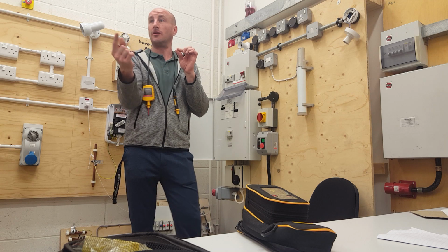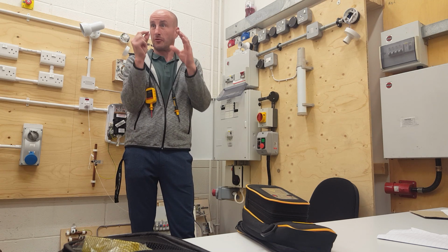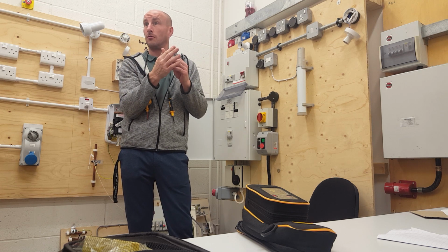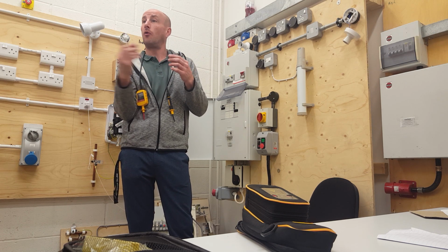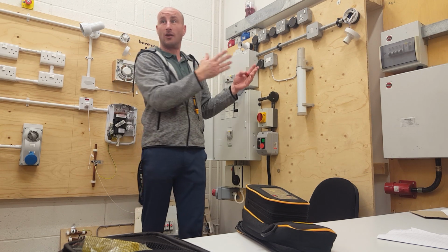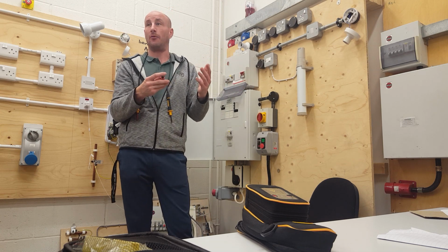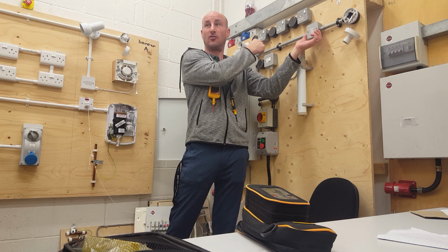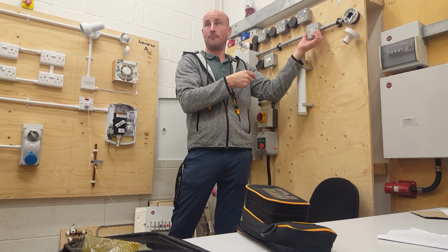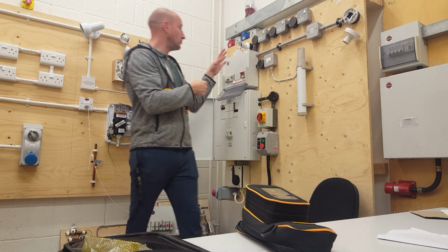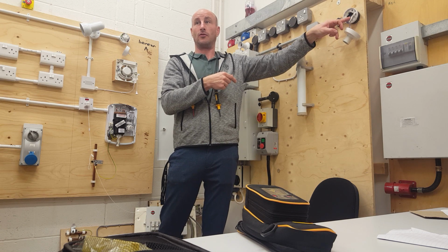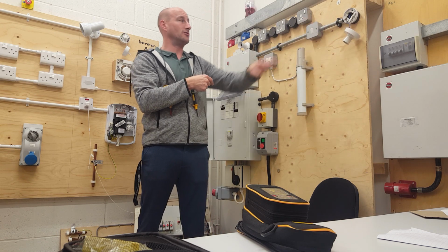You know when you do lighting in the workshop, you don't have any neutrals because they've all got brown sleeving on, haven't they? So they're live wires. You're changing the blue to a live wire. Oh, yeah, I know what you mean. So you don't need a neutral at a switch. You only need neutral where you need power. This doesn't use power, this is just a signal cable. It just breaks the line. The neutral comes straight from here to the light, because you don't need a neutral in here. You don't need a neutral at any switch.